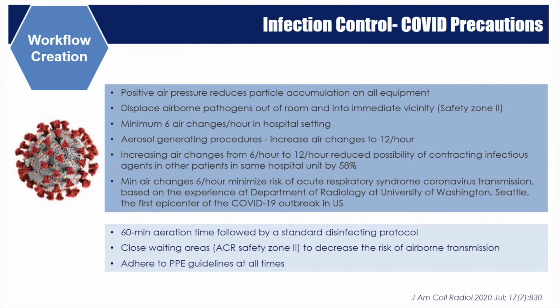The current guideline recommends the minimum application of 6 air changes per hour in hospital setting to prevent infection spreading in the healthcare facility. For aerosol generating procedures, increasing the air changes to 12 per hour is recommended. A 60-minute aeration time followed by a standard disinfection protocol in an MR room is recommended as well after contact with a COVID patient. All the department staff should adhere to personal protective equipment guidelines at all times.